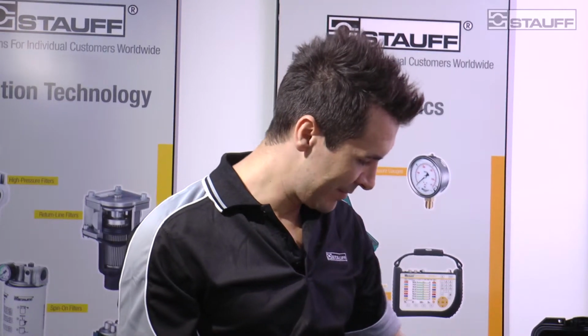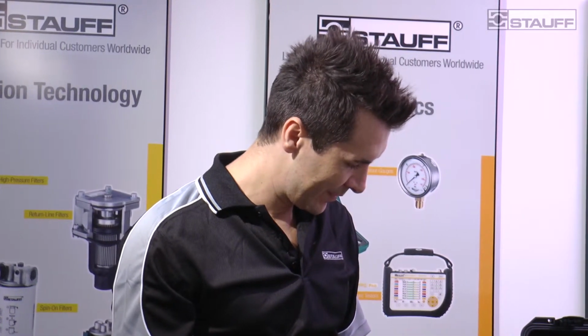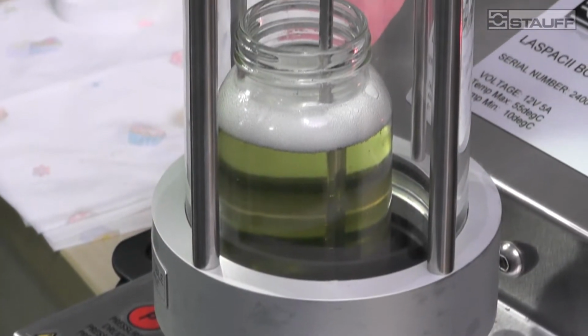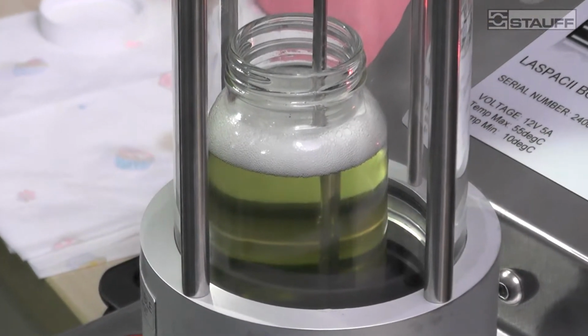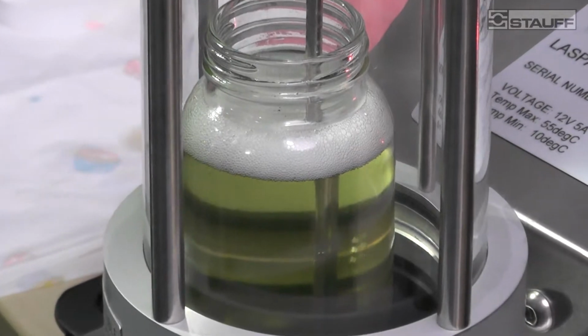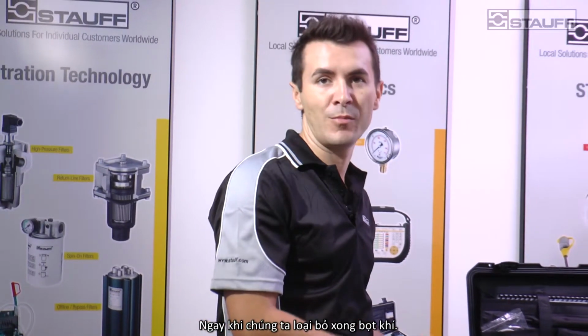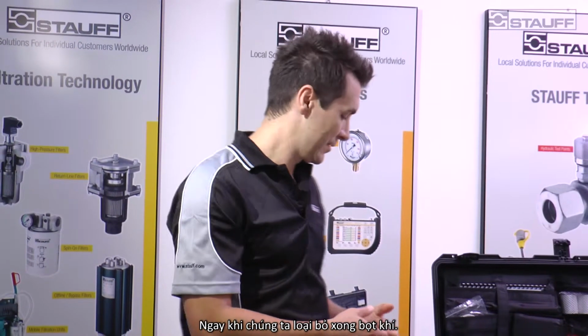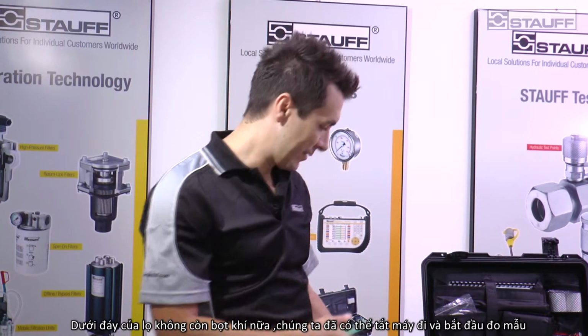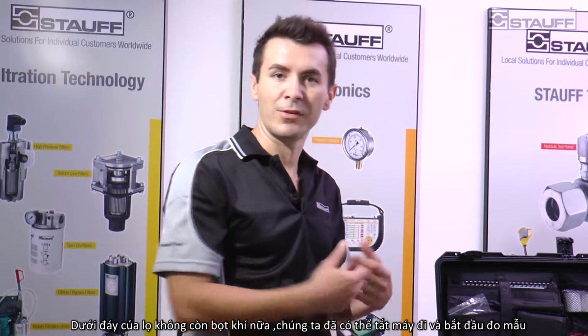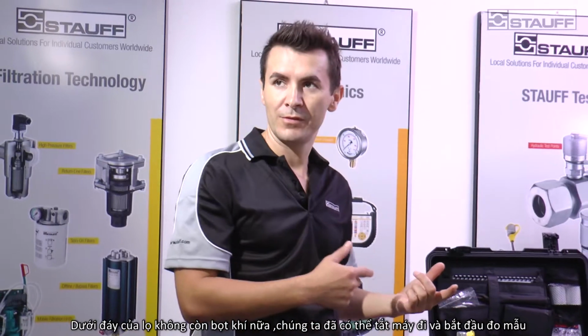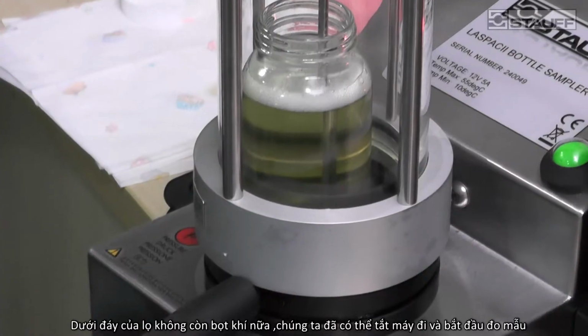Because this is hydraulic oil, it's actually going quite quick. Once we finish removing all the air bubbles, so there's no more bubbles down the bottom, now we are ready to turn it off and then commence the test.